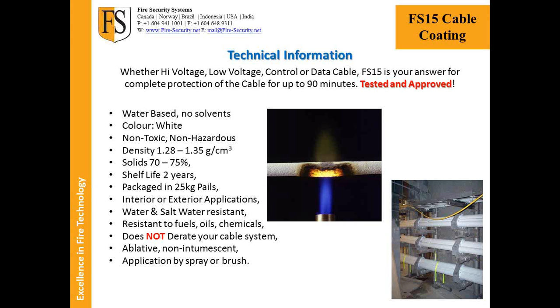How is that? Because you're insulating it to some extent, isn't it? Okay, I'm going to hold you off on that until the next slide, because that's where I'm going to talk about duration. As we discussed, the coating is ablative, non-intumescent. Intumescent means that it expands and protects by insulation. Ablative protects by chemical reaction. The cable coating activates at approximately 80 to 85 degrees Celsius. That's when it starts its chemical reaction and releases its non-toxic, non-hazardous gases around the cable, which stops flame spreading because it takes away all of the oxygen within that region. Therefore, there's zero flame spread of the cable.